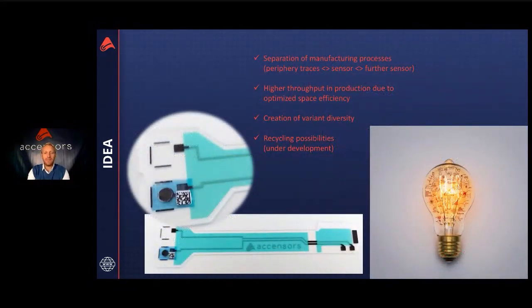And this is the same sensor stripe, the pH sensor stripe I showed you before. And here you see it in the technology of SMD Foilsensors. So this means we have two tracks. They go from the PET side. The PET is connected to the measurement electronics at the top of the stripe. And here is one open area, and on this open area we will place, by a pick and place process, for example, the reference electrode. And the blue SMD foil sticker is the pH sensitive electrode. So we take this electrode sticker, place it on the periphery board with a little bit of pressure, and that's all. Then we have a mechanical fixation and we have an electronic connection. And of course, we have the possibility later to bring it into a recycling or refreshing process.